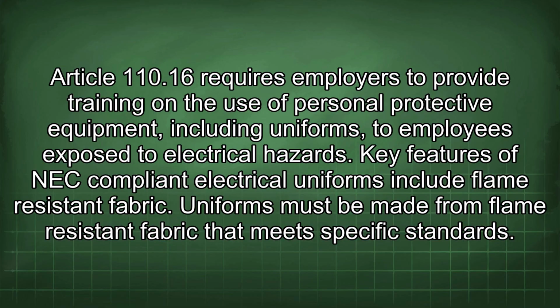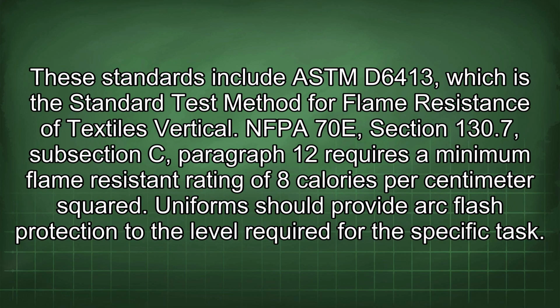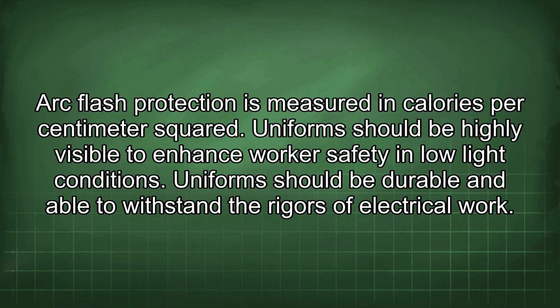electrical hazards. Key features of NEC-compliant electrical uniforms include flame-resistant fabric. Uniforms must be made from flame-resistant fabric that meets specific standards. These standards include ASTM D6413, which is the standard test method for flame resistance of textiles vertical. NFPA 70E, Section 130.7, subsection C, paragraph 12 requires a minimum flame-resistant rating of 8 calories per centimeter squared. Uniforms should provide arc flash protection to the level required for the specific task. Arc flash protection is measured in calories per centimeter squared.